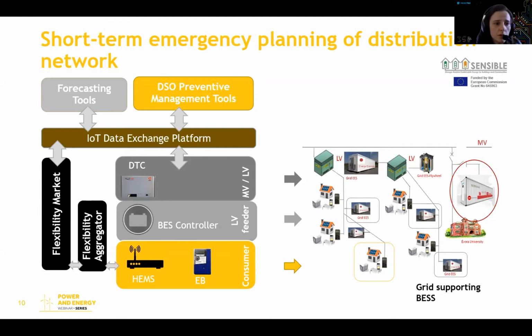that you see on your left, that basically is composed at the local level by the smart meter device, that monitors both voltage and the energy consumption profile every 15 minutes and sends it upstream. Then we have the controllers for the storage devices and the controller at the medium to low voltage substation that collects all the data from the smart meters and also ensures the control of the devices according to the set points that are sent by the high-level management tools.